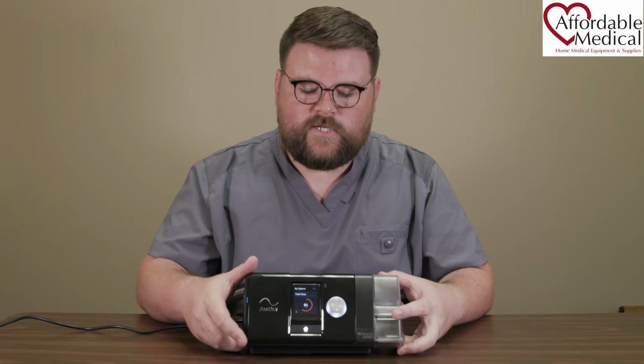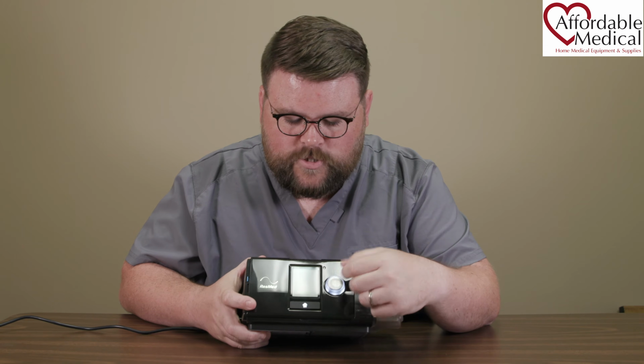Typically on auto, the machine measures and tries to do it for you. In manual, you'll have to use some reasoning to adjust it yourself. For example, if you have condensation in your tubing, think cold tube—simple enough. If my tube is too cold and I'm running warm air through it, I'm going to get condensation, so I need to warm my tube up. Cold tube means condensation. How do I fix it? I heat the tube up, and we do that by adjusting the tube temperature.